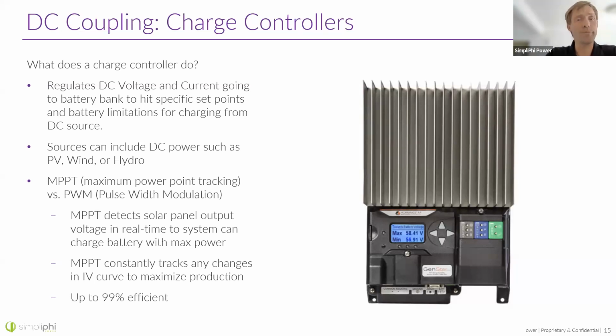MPPT controllers can be very efficient, up to 99% efficient. That means 99% of the energy they're drawing off that solar array, they can direct accordingly. The other 1% ends up as heat, which is why you see those cooling fans on top of that MPPT controller.